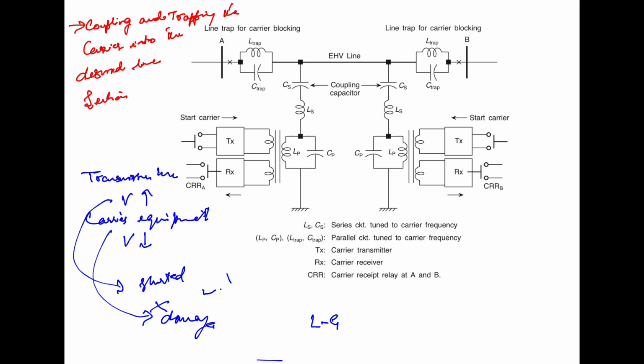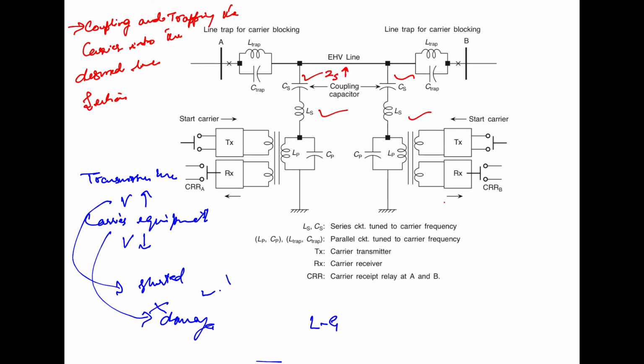Now, in this case you will see the line traps, which confine the carrier signal into the desired line section. Now let us analyze this figure. Here we have the coupling capacitor.